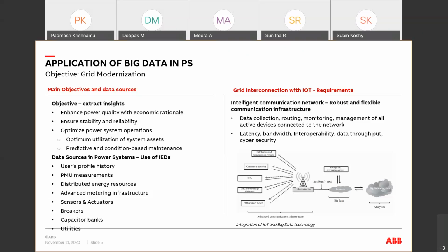For example, let us take the data from the PMUs. When we take the data from the PMUs, there is an optimal application of time synchronized phasor data, which leads to the development of wide area measurement systems. So WAMS is a powerful approach to identify inter-area oscillations in a large grid. So if you have to utilize the data from the PMU, you could easily utilize it, and you can look at it from a perspective of creating a stable grid, because you can identify inter-area oscillations in a large grid.